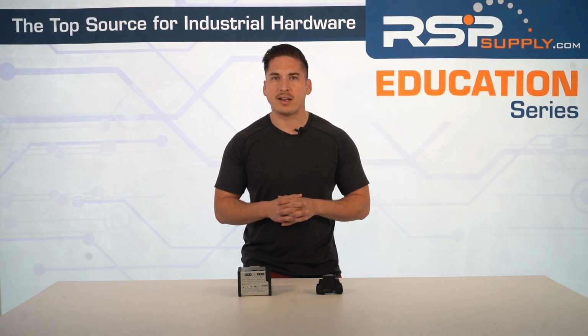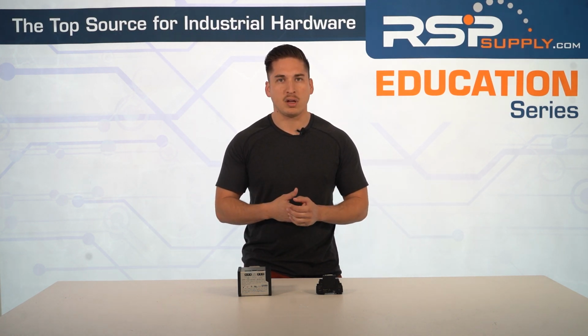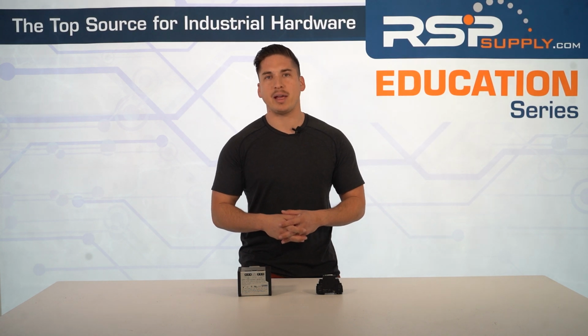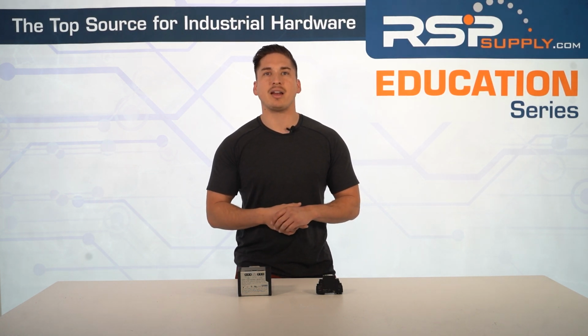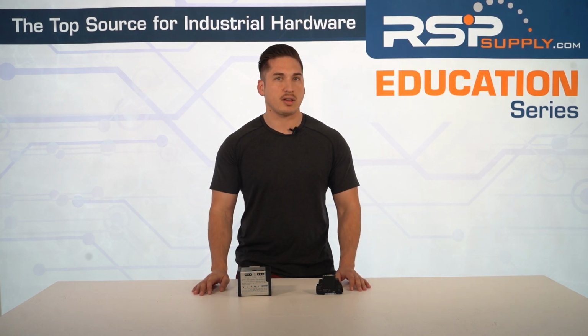A data surge is a little different. It occurs when excessive voltage travels along communication lines like Ethernet, RS-232, or other signal and data transmission networks, many of which are in control panels. Causes for data surge include EMI (electromagnetic interference), lightning strikes, and improper grounding or shielding. Data surges corrupt communication signals, damage ports on devices like PLCs, HMIs, and SCADA systems, and cause data loss or erratic system behavior. In industries relying on accurate data and communication, even a small data surge can lead to significant issues.